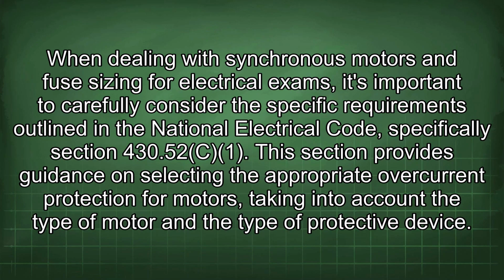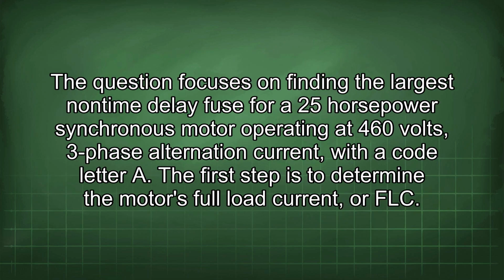When dealing with synchronous motors and fuse sizing for electrical exams, it's important to carefully consider the specific requirements outlined in the National Electrical Code, specifically Section 430.52(C)(1). This section provides guidance on selecting the appropriate overcurrent protection for motors, taking into account the type of motor and the type of protective device. The question focuses on finding the largest non-time delay fuse for a 25 horsepower synchronous motor operating at 460 volts, 3-phase alternating current, with the code letter A.